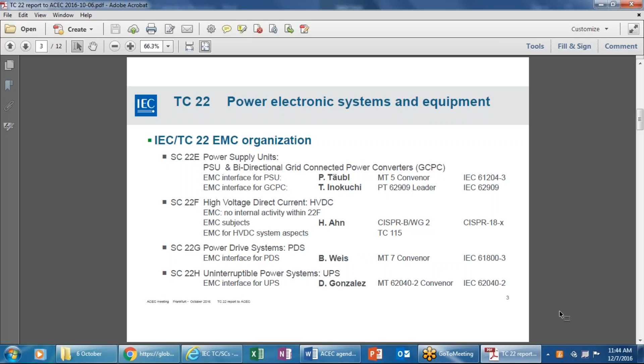The point being is they are saying, look, there's a billion with a B products out in the market that have put signals on between 2 kilohertz and 150 kilohertz because there's no limits that applied, except in some cases like induction cookers, which were below 150 kilohertz. And there's no way you're going to suppress what is there to give a better signal-to-noise ratio for the control of the smart grid and the smart system, if you will.